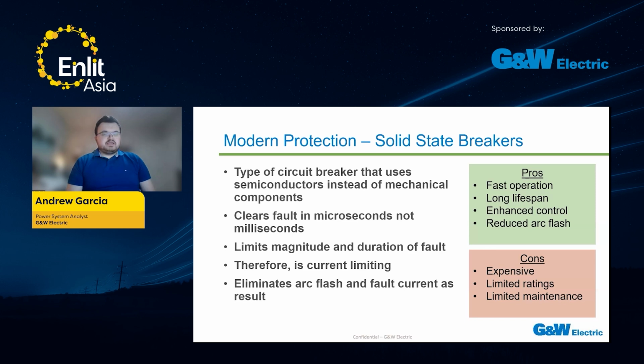The big plus for these solid state breakers is that they ultimately clear faults in microseconds, not milliseconds. So a fraction of an electrical cycle. Ultimately, they limit the magnitude and duration of the fault, and since they clear faults in less than half a cycle, they're therefore current limiting devices. As a matter of fact, they almost entirely eliminate arc flash and fault current as a result through those breakers. Now, that sounds way awesome, right? Really good. And you're right.